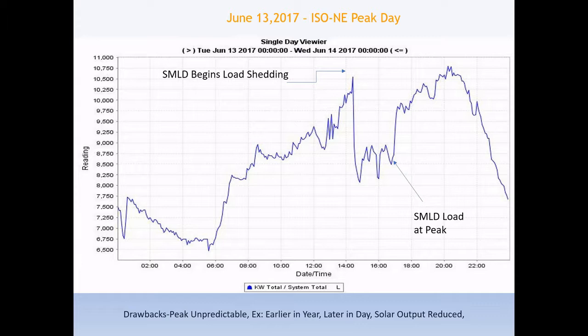This slide shows the meat and potatoes of the project — the peak day load shape on the ISO New England peak day, June 13th, 2017. You can see we were sitting right around 10 megawatts and during the peak period we were down to about 8.5 megawatts, showing the work the battery does for us during those time periods. Being able to shed that much load prevents dirtier generators from running, and I think this also helps eventually on transmission costs — we won't have to build so much transmission if we can control distributed energy better. Drawbacks: peaks are unpredictable and batteries are a finite source, so you have to spread discharge out.